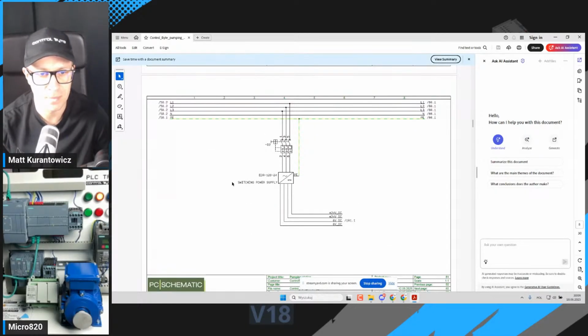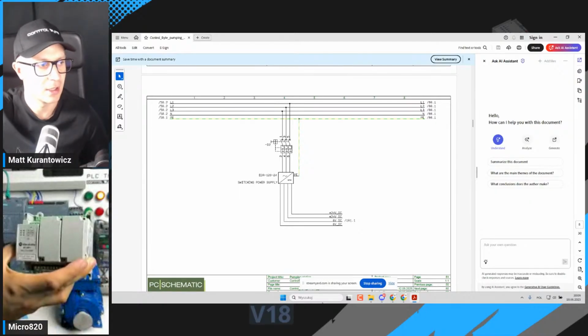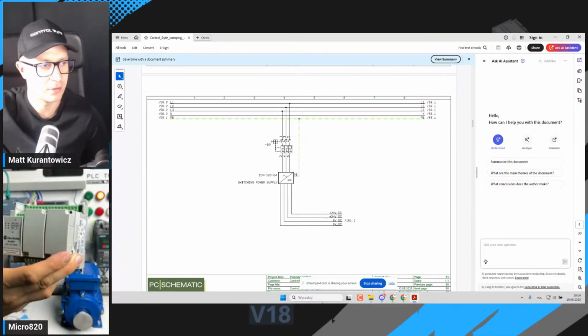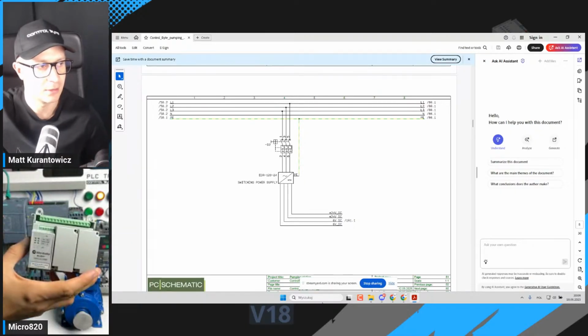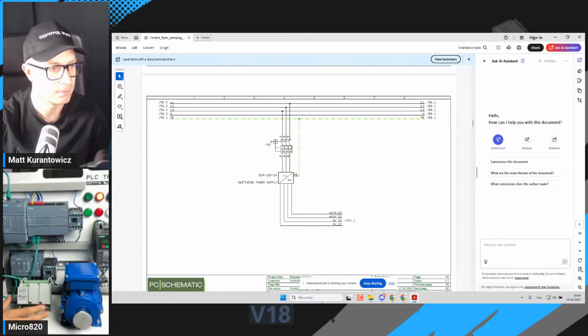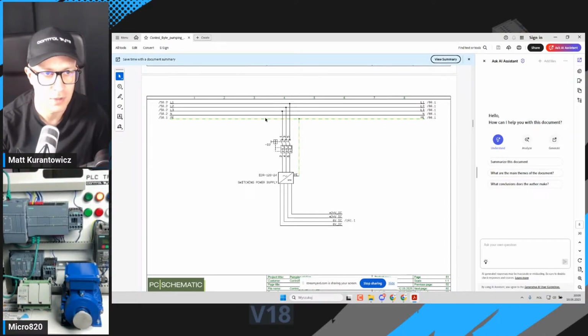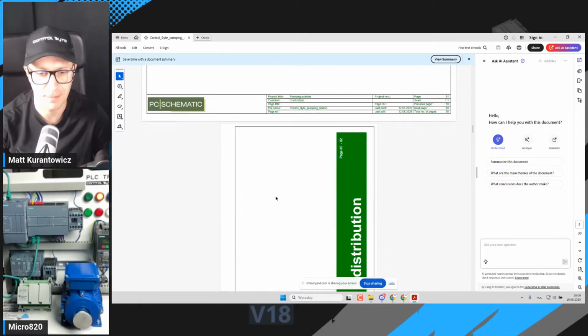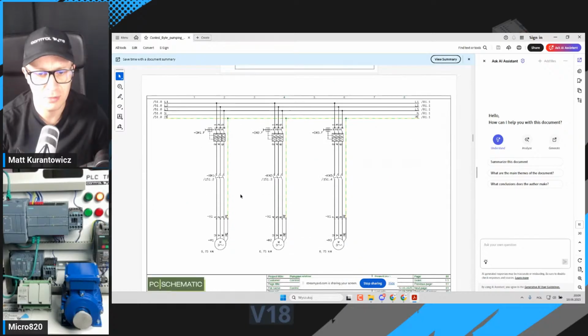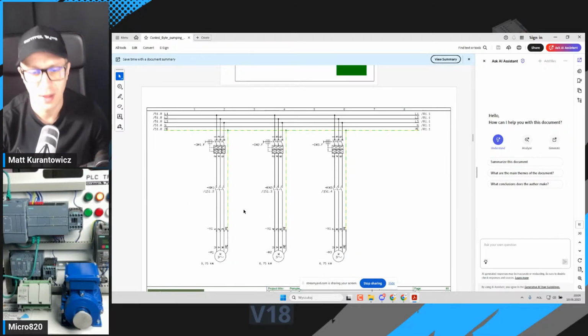Here we have the main switch, phase control sensor here, then we go to the switching power supply, because this PLC is supplied with 24 volts DC. So here we have a mains power supply, and here we have 24V DC supply. Then we have power distribution, and here we control 3 motors in this pumping station, so we have contactors and, of course, 3-phase motors.